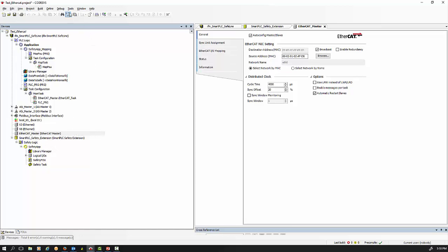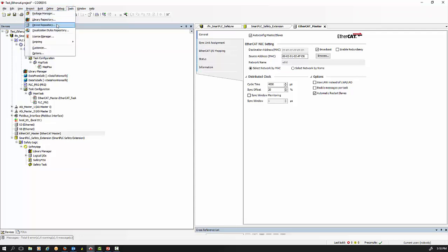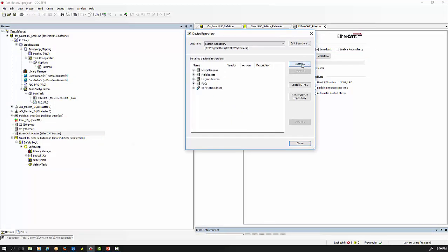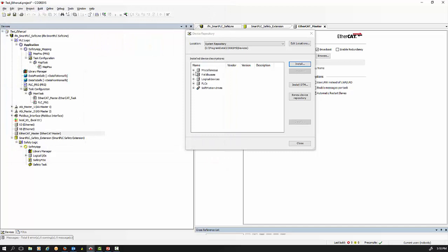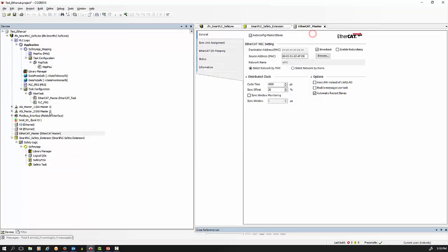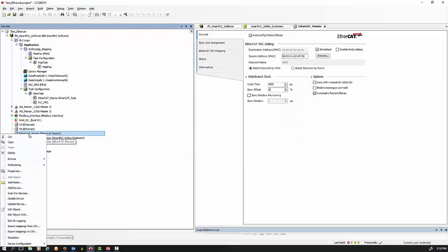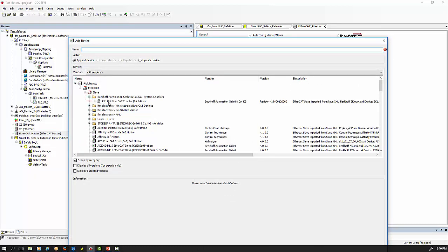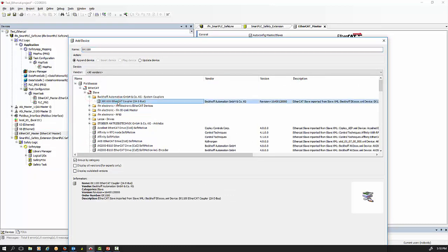You also need to install the ESI files for EtherCAT. Once you've downloaded those or got them from your IFM representative, go to Tools > Device Repository, click 'Install', find your ESI files, and install them. They will then appear in the device repository.